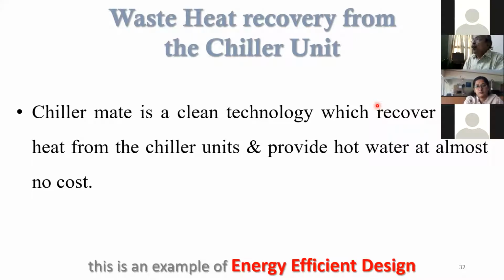Imagine a condition where, instead of throwing that heat out, you utilize that heat to generate hot water for the same building. Then you are moving in the correct direction of energy efficient design, because the heat removed from the building is not thrown to the external atmosphere, making it warmer. Instead, you economically use it to generate hot water supply within that particular building. So ChillerMate is a clean technology which recovers waste heat from the chiller unit and provides hot water at almost no cost. Let me show a video on this.